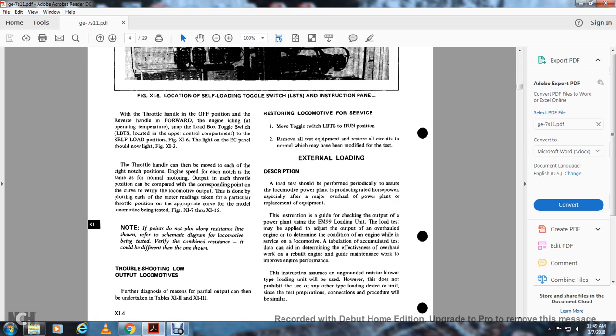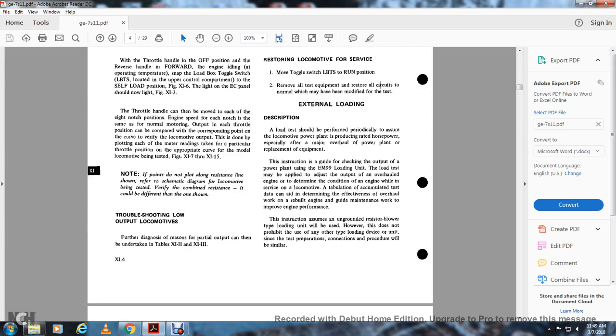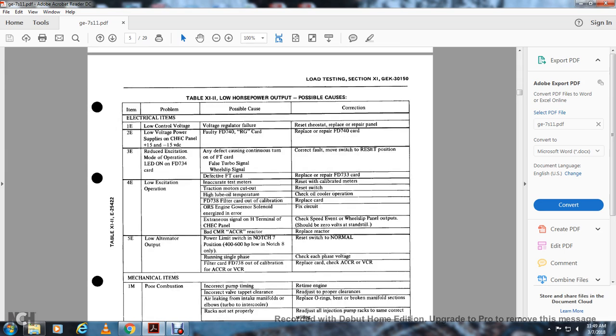This instruction assumes that an ungrounded resistor blower type of loading unit will be used. However, it does not prohibit the use of any other loading device or unit, since the test preparation and connection procedure will be similar. Item, problem, possible cause, correction.